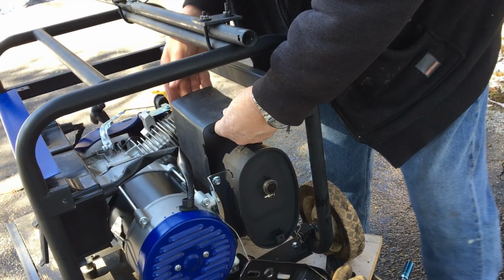The heat shield is hard to evaluate. However, in theory, the lower the operating temperature of the alternator, the more hours one should get before insulation failure. In my testing, I saw the shield cut the surface temperature by 32 degrees on a day when the ambient temperature was 43 degrees. Without the heat shield, the surface temperature of the stator rose to 183 degrees. During the test, the generator was loaded to less than 40% of its rated capacity.